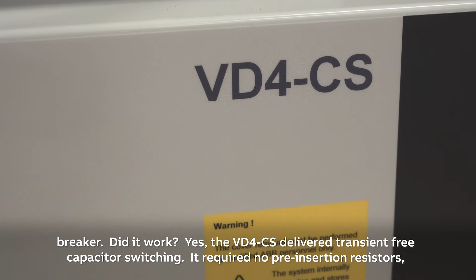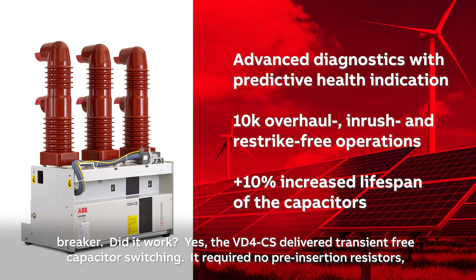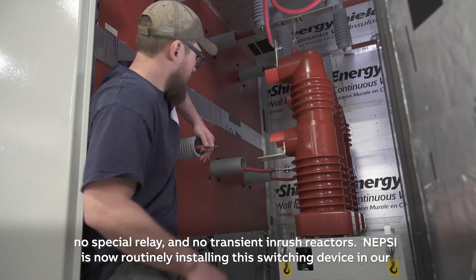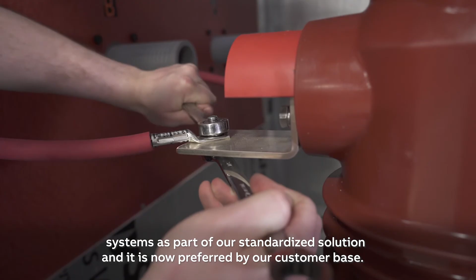Did it work? Yes, the VD4CS delivered transient-free capacitor switching. It required no pre-insertion resistors, no special relay, and no transient inrush reactors. NEPSI is now routinely installing this switching device in our systems as part of our standardized solution, and it is now preferred by our customer base.